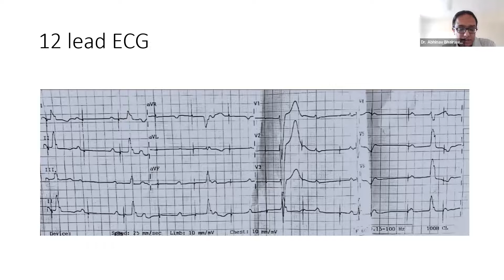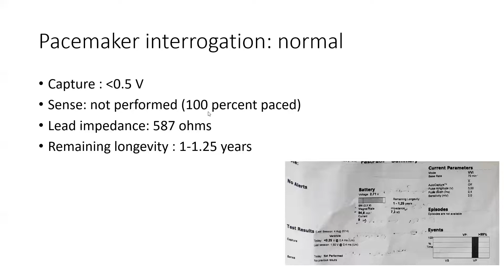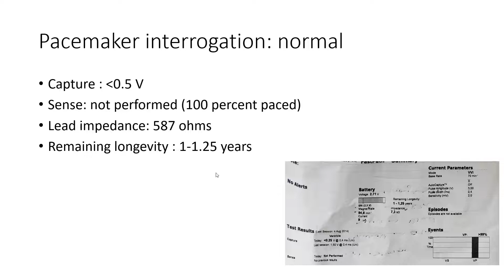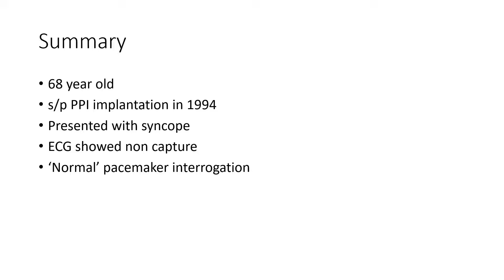So because of the history of syncope and failure to capture on the ECG, he was immediately taken to the interrogation room. However, the pacemaker interrogation revealed a capture threshold of less than 0.5 volt, an impedance of 587 ohms, and a remaining longevity of 1 to 1.25 years. So this was essentially a normal pacemaker interrogation. So to summarize, 68-year-old gentleman, status post pacemaker implantation in 1994, presented with syncope, ECG showed non-capture and a normal pacemaker interrogation.